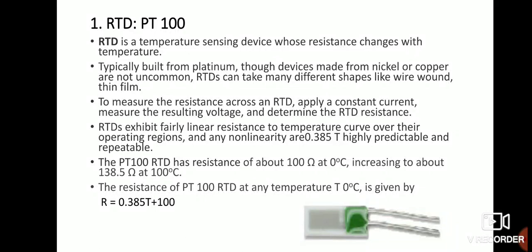To calculate the resistance of PT100 at any temperature T degrees Celsius, the equation is: R = 0.385 × T + 100. If T = 0°C, resistance = 100 ohms. If T = 100°C, then 100 × 0.385 = 38.5, plus 100 = 138.5 ohms. So at any temperature T we can calculate the resistance of PT100.